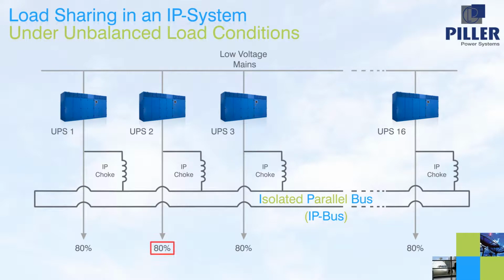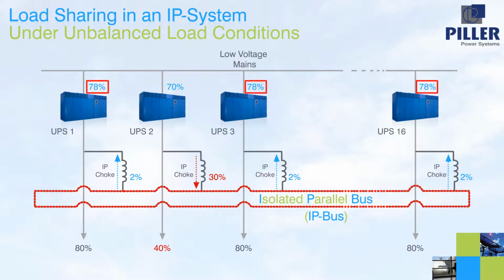Supposing now that load number 2 is reduced to 40%. In this situation, UPS number 2 is still carrying 70% of load, feeding 40% into its associated load and 30% into the IP bus. The other 15 units are each taking 2% from the IP bus, which results in a reduced power of 78% for each unit, feeding its 80% load.